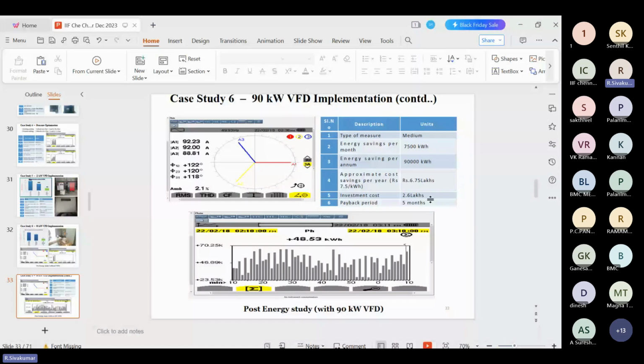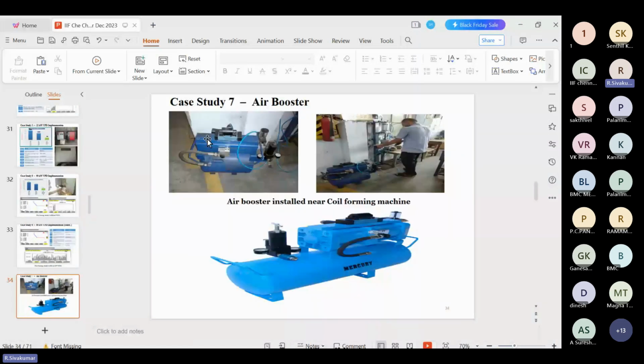Another important example: in one pump industry, they have a captive foundry along with the pump industry. For the coil forming machine, there is a cylinder. The pneumatic air requires almost 9 bar pressure. Due to this, the compressor head was trimmed and the generation pressure was raised to 11 to 12 bar. But other areas, except this coil forming machine, needed only 6 to 6.5 bar. So we suggested adapting an air booster on that particular equipment. The air booster principle is that whatever input is given, it is amplified 2 times. So the total air generation pressure was reduced.